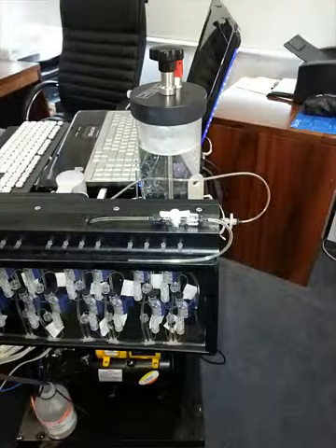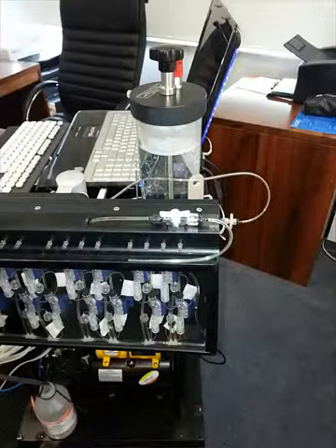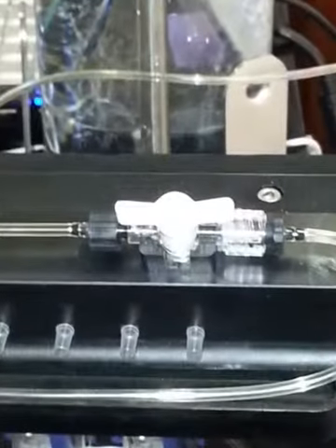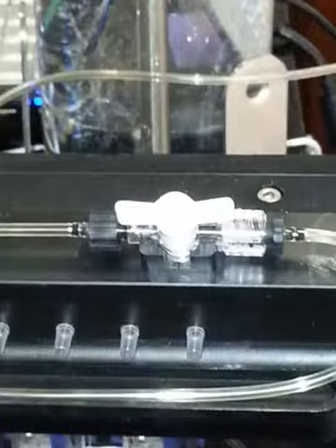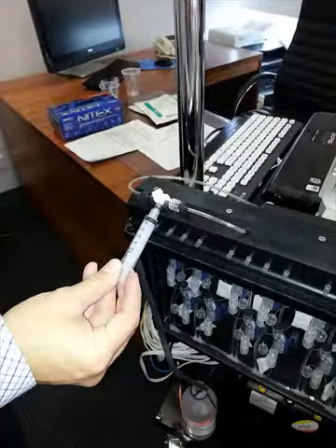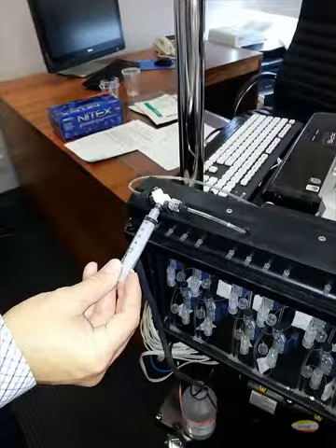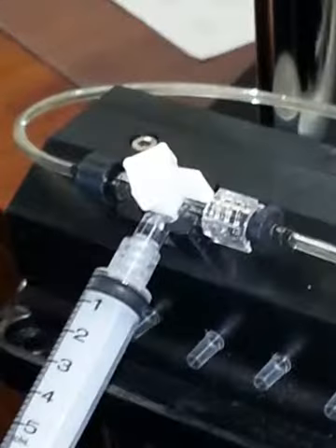The next step is to prime the pump with water, ensuring that air is expelled from the manifold. First, open the water tap at the outlet of the water manifold. This ensures that water can flow through the manifold and into the wastewater area. Next, rotate the three-way tap at the inlet of the pump so that the lever, which indicates the off position, is pointing to the right along the manifold. You will also need to open the tap at the base of the water reservoir.